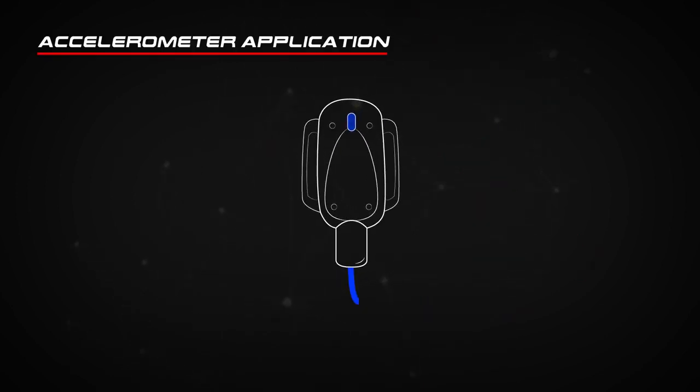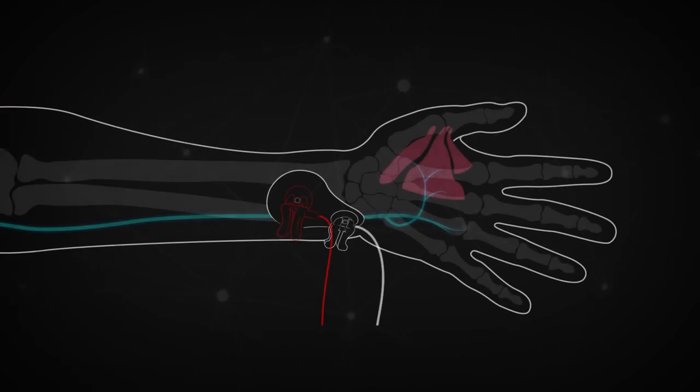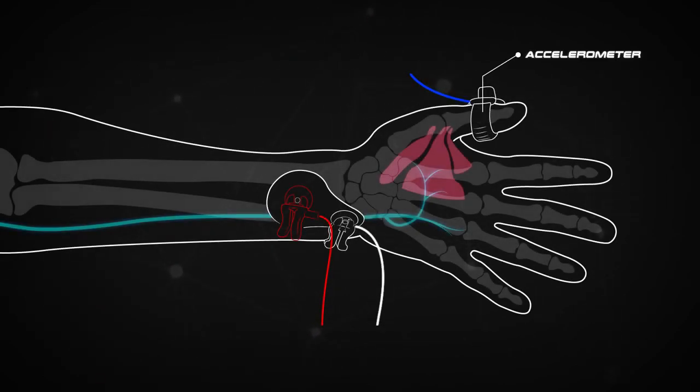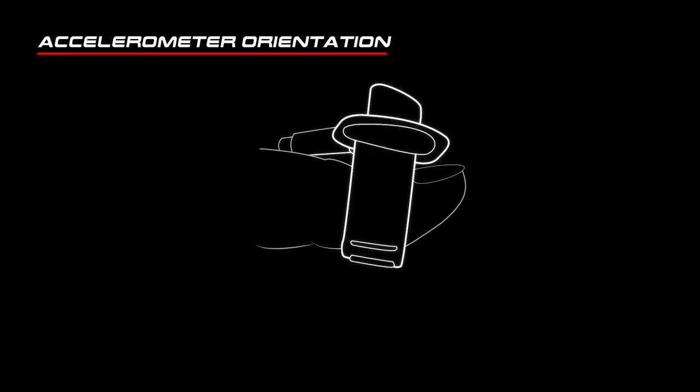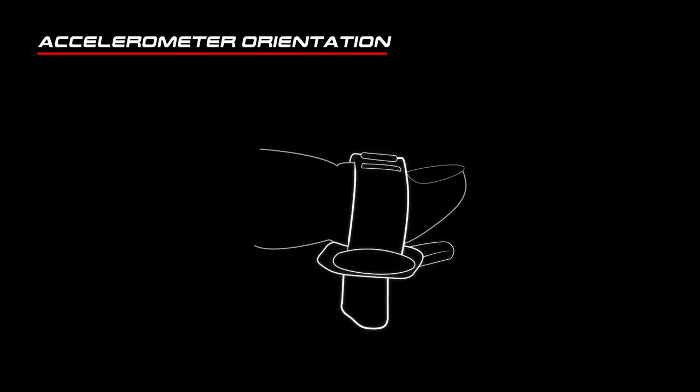Accelerometer application. Due to the fact that the ulnar nerve stimulation will contract the adductor pollicis, the accelerometer should now be applied to the patient's thumb. The accelerometer contains three-dimensional technology which allows for the accelerometer to be oriented in any way and therefore requires no calibration.